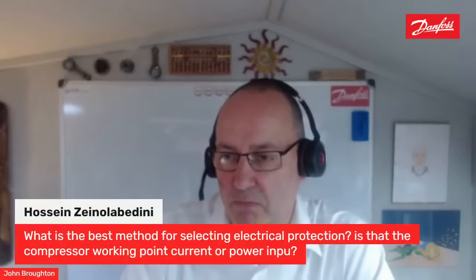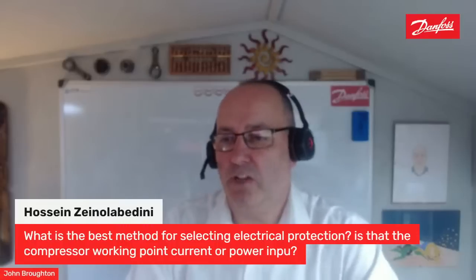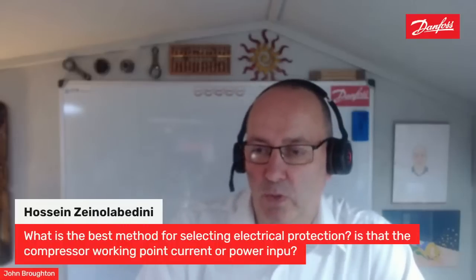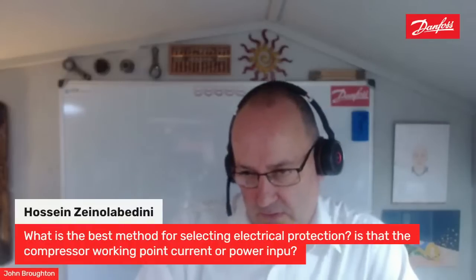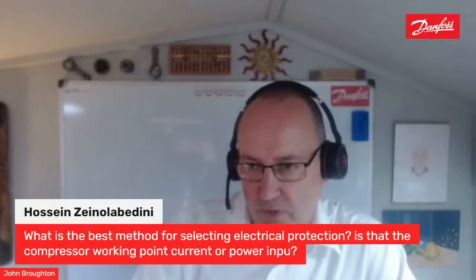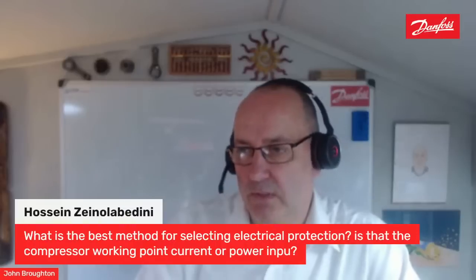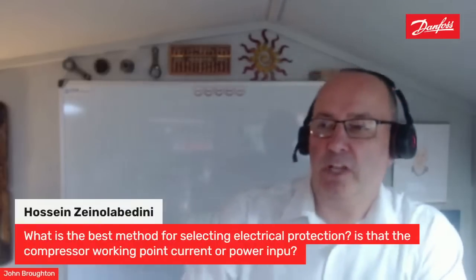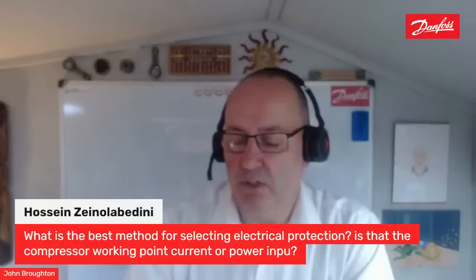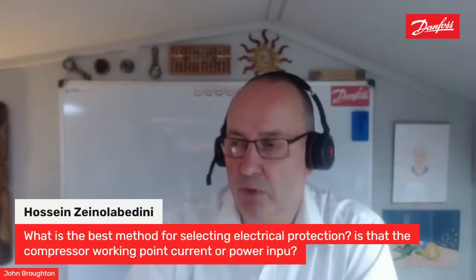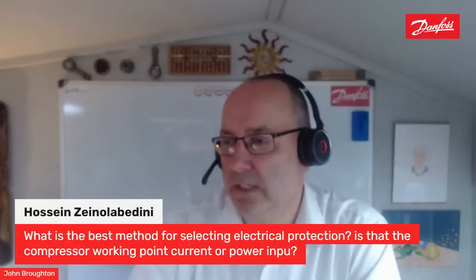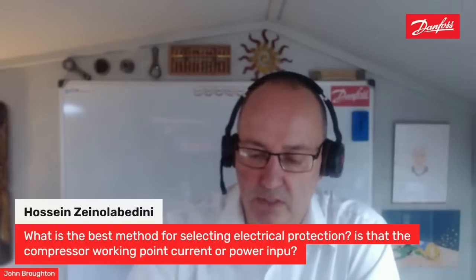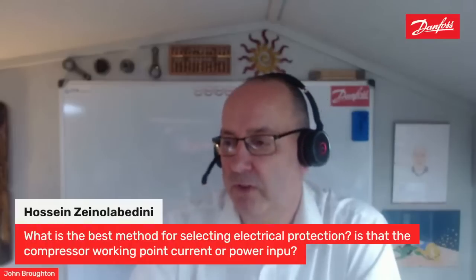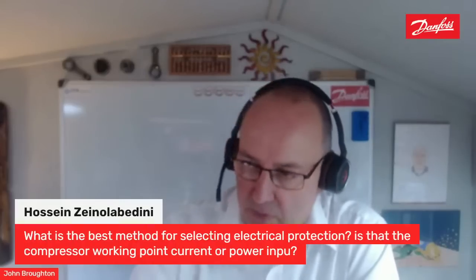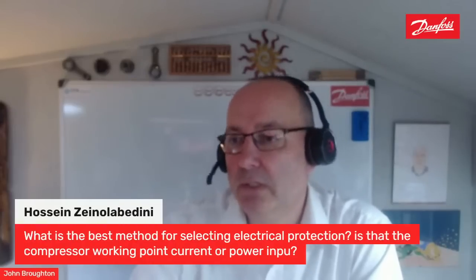Another question from LinkedIn, from Hosin. What is the best method for selecting electrical protection? Is that the compressor working point, current or power input? You are trying to protect your compressor. So that's basically what you've got to base your electrical protection on, the maximum continuous current of that machine. Base it on that for sure.